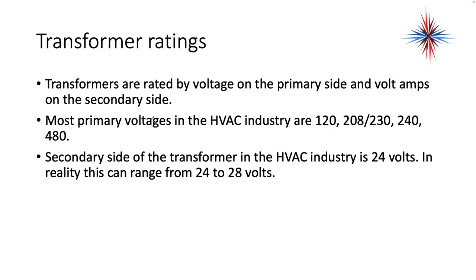Transformers are rated by the voltage on the primary side and volt amps on the secondary side. Most primary voltages in the HVAC industry are 120, 208-230, 240, and 480. The secondary side in the HVAC transformer industry is 24 volts. In reality, this range can be between 24 and 28 volts. Most transformers I've come across are actually producing 26 volts without a load, and with a load they're around 24 volts.